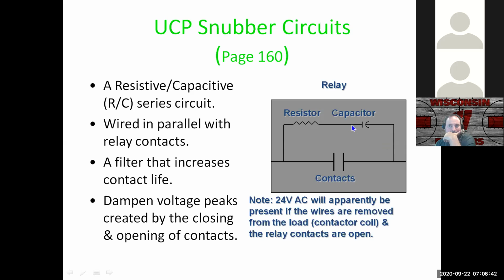When the load is connected, the load basically absorbs that little trickle voltage that goes through this circuit. But when you disconnect the load, what you're going to get is a phantom signal. As soon as you disconnect the load, it's going to send 24 volts out on this wire. And you're going to read 24 volts, and it may not be a closed circuit. It may just be this phantom voltage trickling through this circuit.